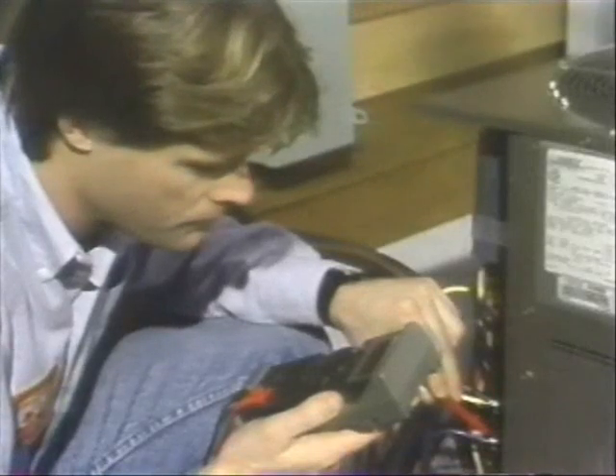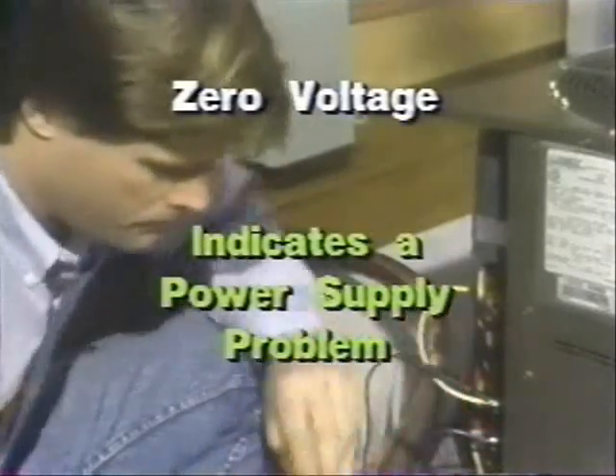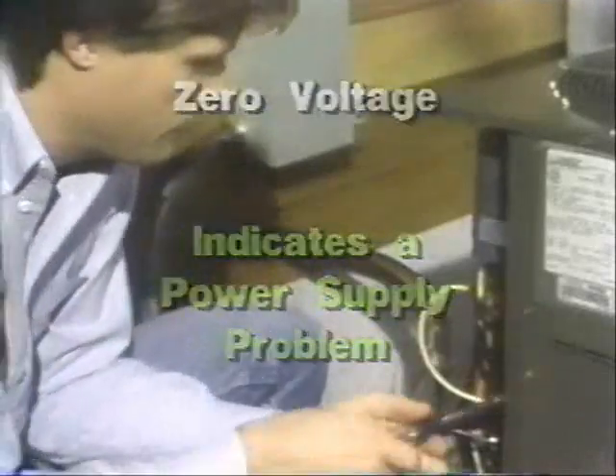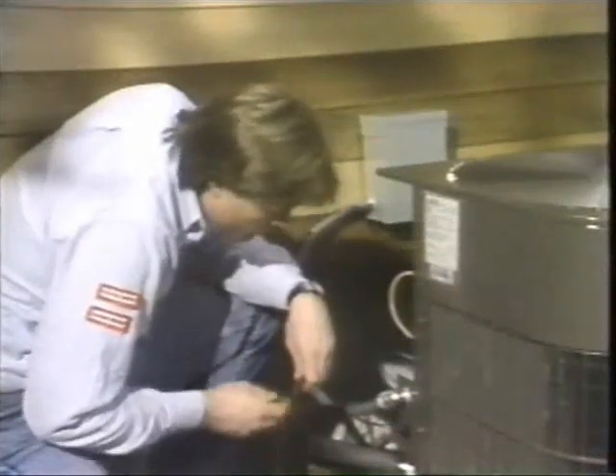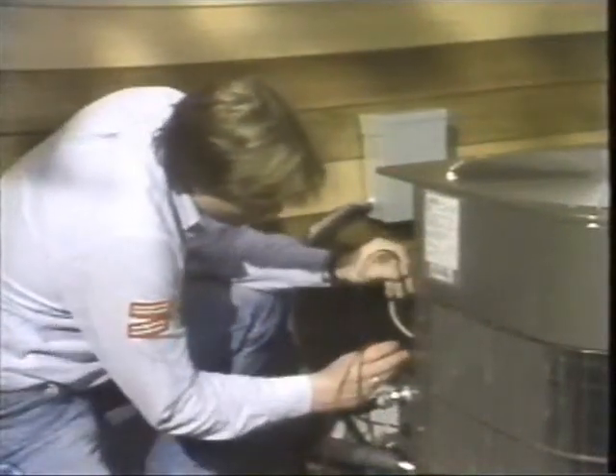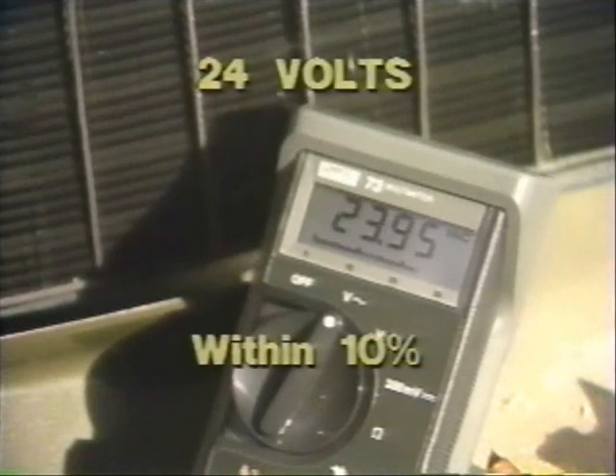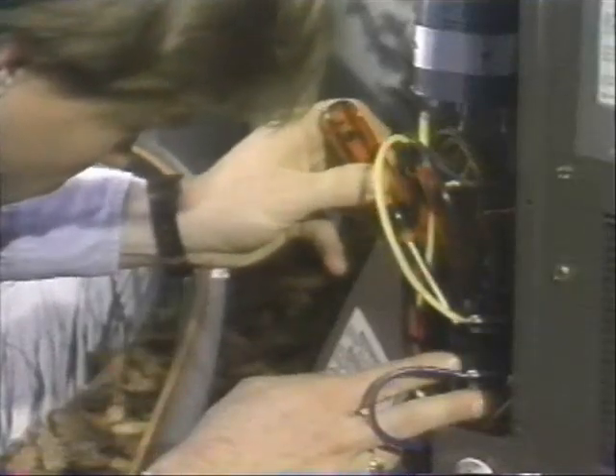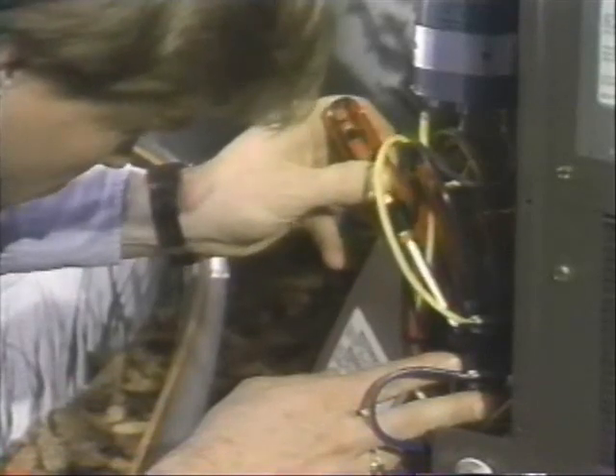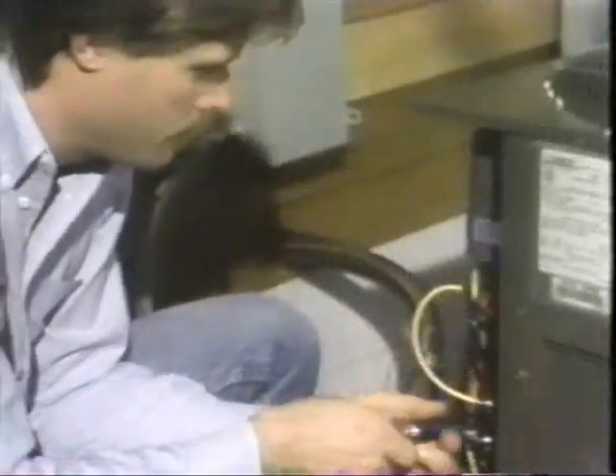Now, back to the coil voltage check. 0 volts on the coil indicate a power supply or control circuit problem. A contactor that buzzes but does not pull in probably indicates low control circuit voltage. Check the voltage at the coil terminals. The voltage on the contactor must be within 10% of its rating. A mechanical problem with the contactor armature can also keep it from pulling in. If that's what you find, you'll have to replace the contactor.